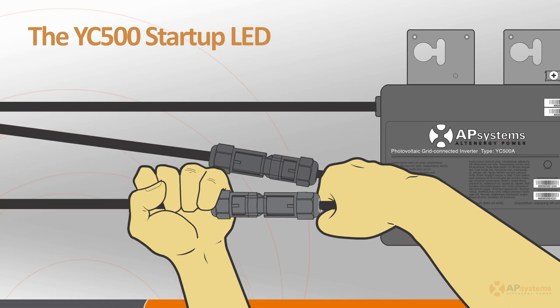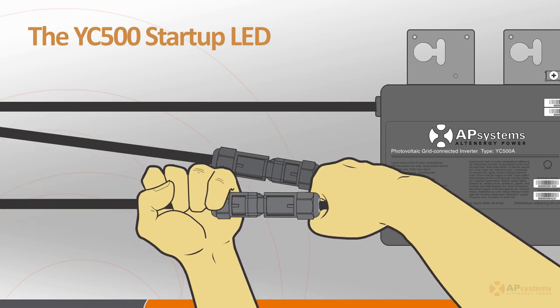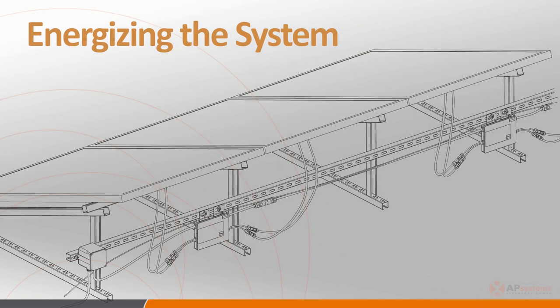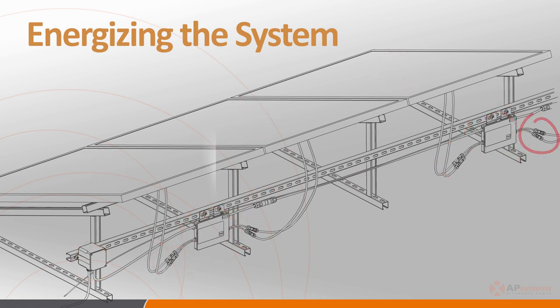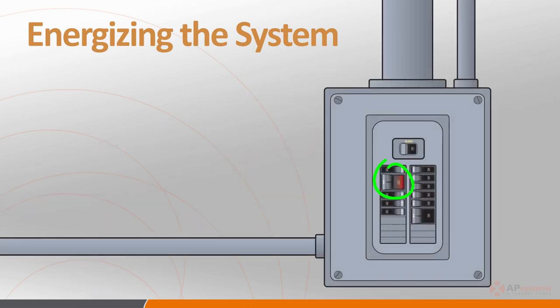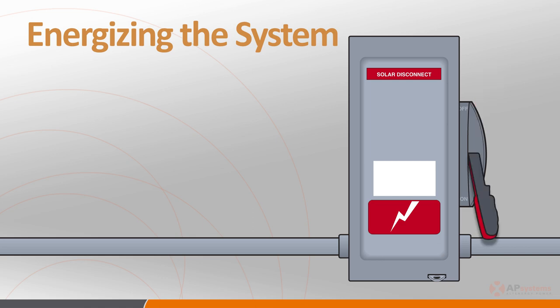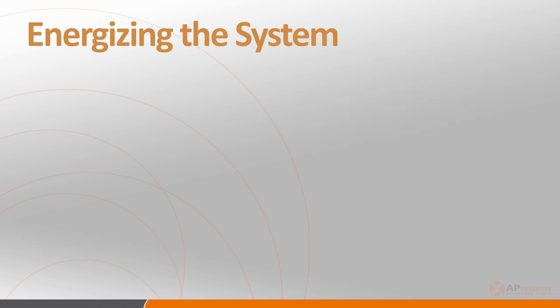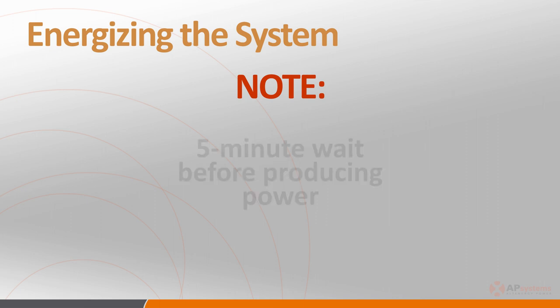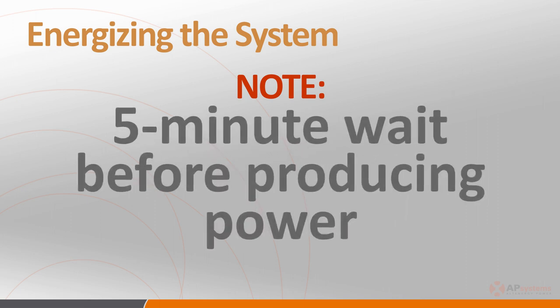This startup indication only happens when the DC power is applied to the PV side of the connected inverter. Check the DC connectors if you don't see the green startup LED flash. With the PV modules and inverters in place and all connections thoroughly checked to make sure they're secure, you're ready to energize the system. First, turn on the AC circuit breaker associated with each microinverter AC branch. Next, turn on the main utility grid disconnect. Note: as a safety precaution against potential islanding, the system will not start producing power for a full five minutes after it detects the presence of the grid.